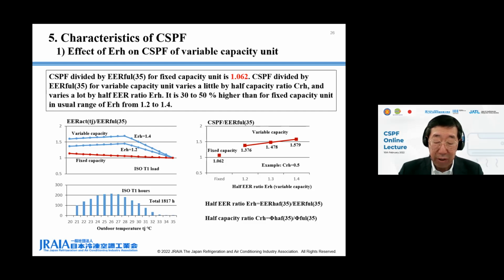This page shows effect of half ER ratio ERH on Cspf of variable capacity unit. The upper left figure in this page shows actual ER divided by 35 degrees C full ER at each outdoor temperature TJ for fixed capacity and variable capacity unit. 35 degrees C full ER is same for both fixed capacity and variable capacity examples here. Half capacity ratio CRH is 0.5 and half ER ratio ERH is 1.2 and 1.4 for variable capacity unit examples.